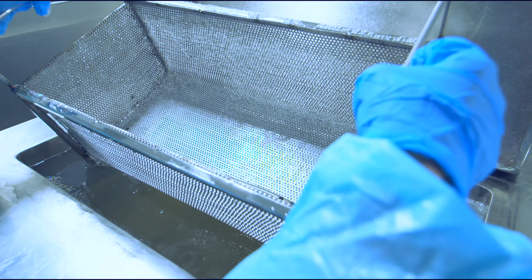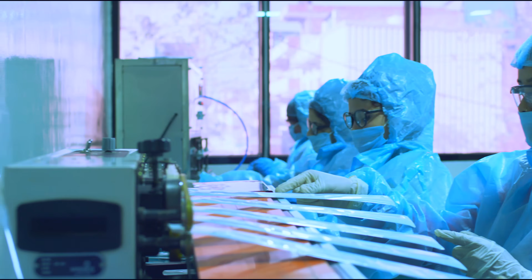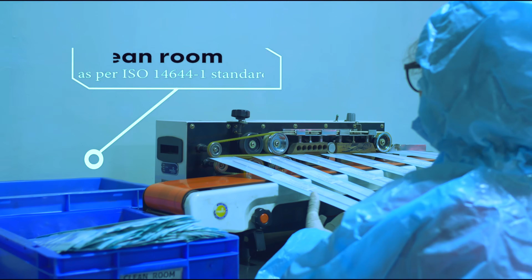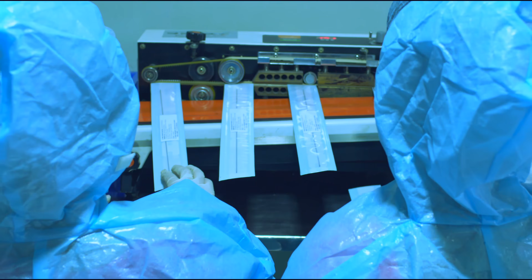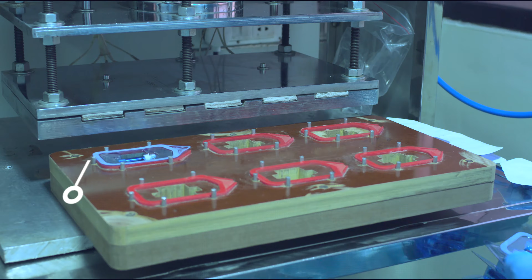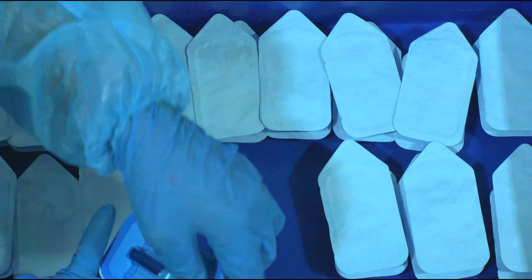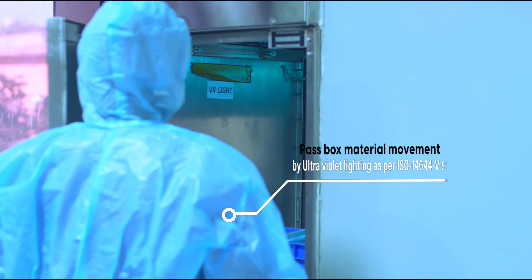So, before final packaging, all products entering the clean room undergo a secondary ultrasonic cleaning process to ensure human-touchless packaging practices and get the safest product packaged. Packaging is done by well-qualified and specially trained people inside the clean room for maximum safety of the product. Every single implant is transferred and processed in a clean room facility made as per ISO Class 7 standards through special pass boxes right up until the minute it leaves our factory, to ensure that men and material flow is streamlined and separated. This also means we have complete control over the quality of the products made.